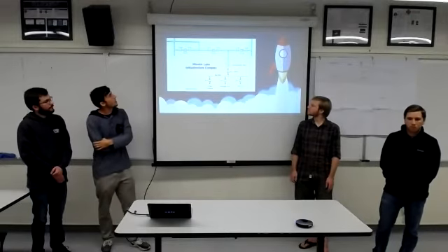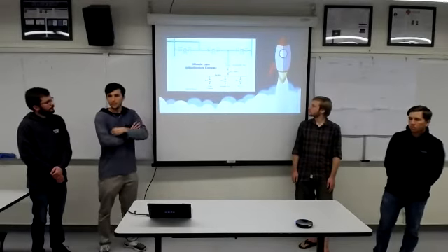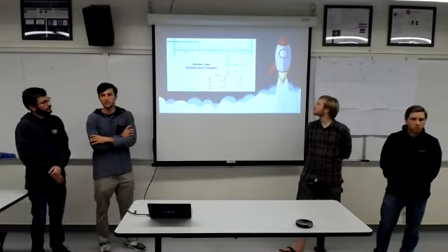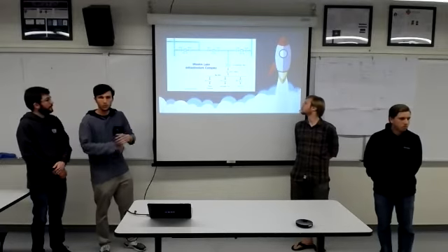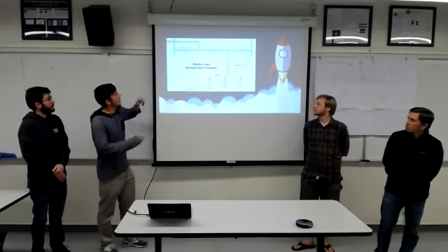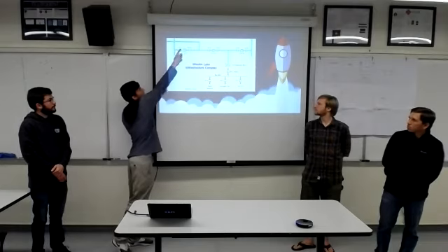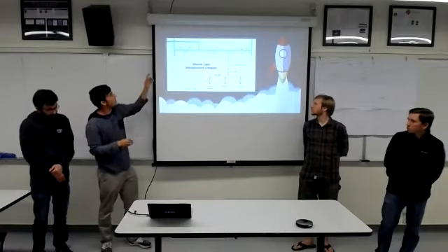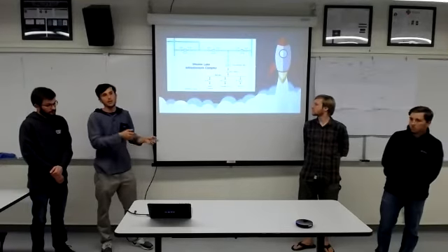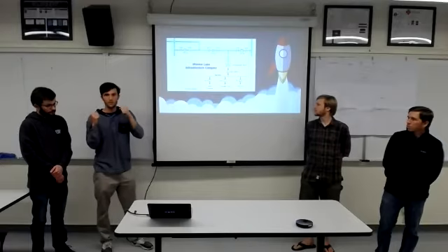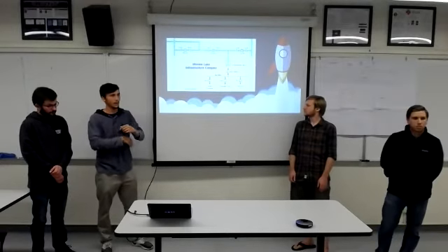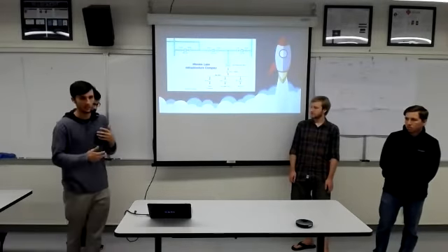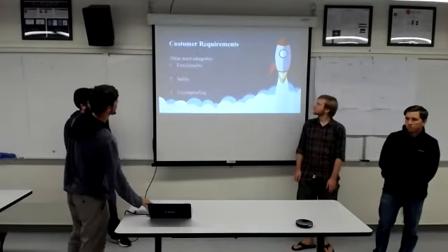And so the idea is we have all the logic that a normal actual power grid has. So in a use case, if a circuit breaker went down, Lefty or one of his engineers would close both of these switches. Not shown on the grid is there's going to be a switch in parallel with these 3 components that they'd be able to close when the circuit breaker goes down, so that the facility would still receive power. They'd then open both of these switches, remove the same circuit breaker, put in a new one, and then reverse that process. So that's a basic use case for if a circuit breaker went down.